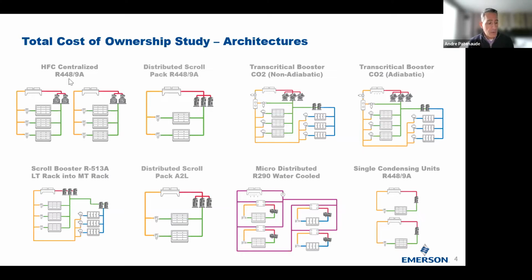So some of the factors that we considered were compressors, of course, the refrigerant, as you see, the number of compressors were all listed in our details. We looked at minimum head pressures. They may change slightly from one architecture to the other to support industry standards. We looked at low temp TDs, medium temp TDs, 10 and 15 degrees. Some systems had case controls and some had mechanical expansion valves. That was factored in all those costs. We also looked at the charge, so how much charge we estimated when we designed these systems, and leakage rates, because depending on the size of the system and how much piping there is, your leakage rates will vary. So we factored all that in when we calculated LCCP, energy, and costs. So next slide, please.